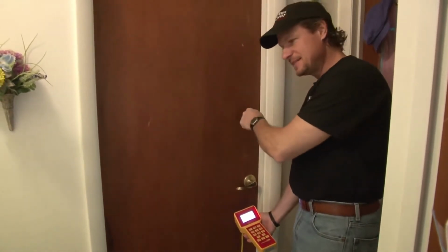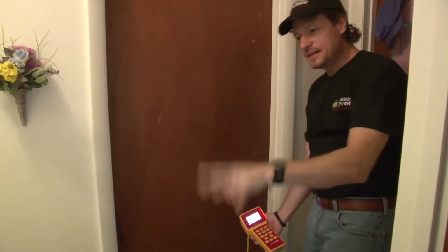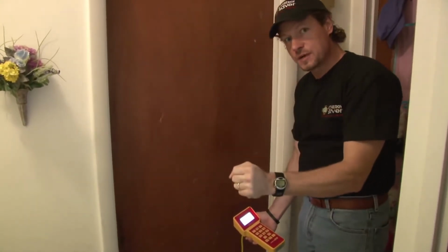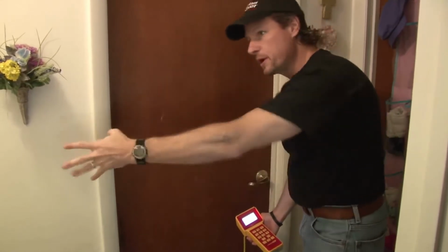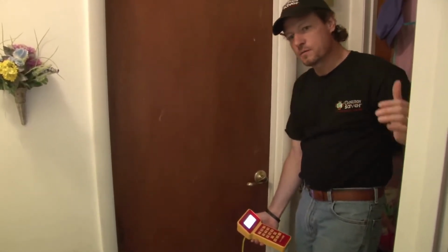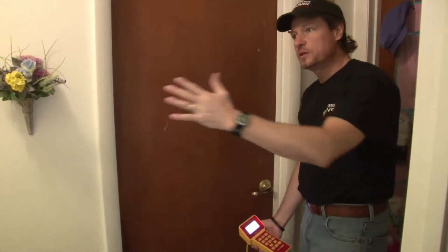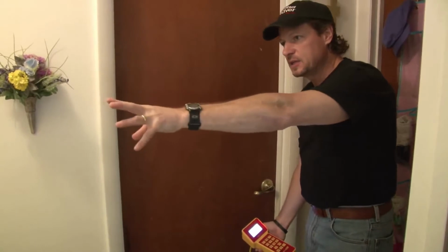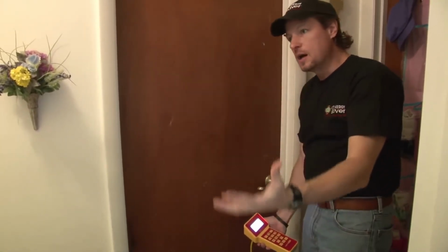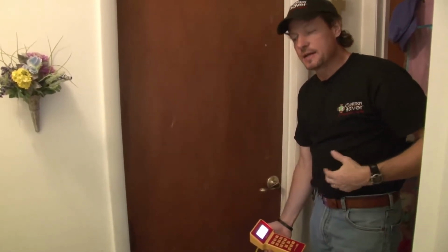That means that side is going to push air out of the house, and on this side, the main area, the living area, the kitchen and so forth, we're depressurizing it because we're taking more air from it than we're putting back into it. We're putting a disproportionate amount of air into the bedrooms that cannot then get back. So what we're doing in the main kitchen and living area is sucking air in through the walls, through the windows and doors, from the attic and from any air holes to the outside to make up for it.